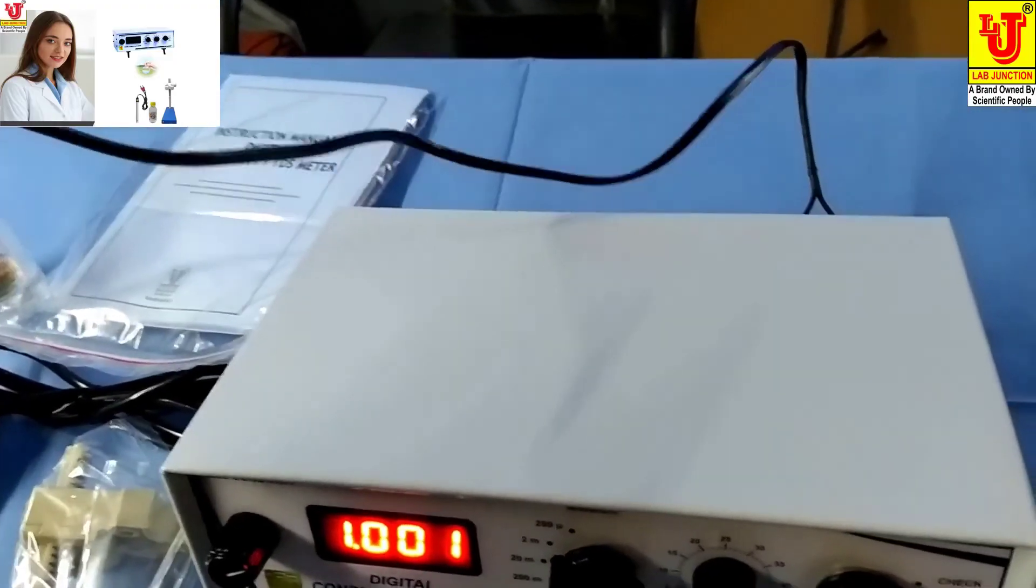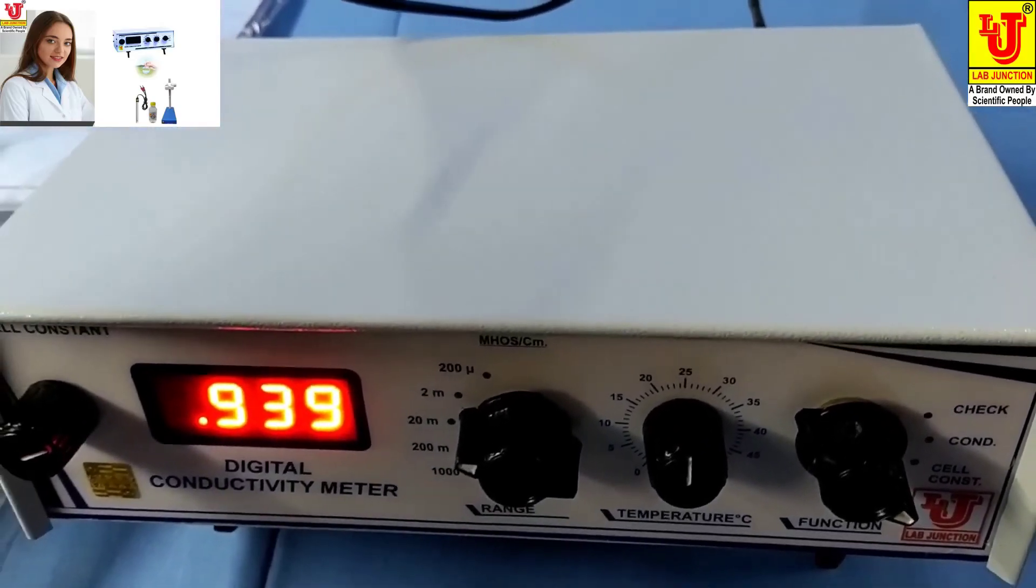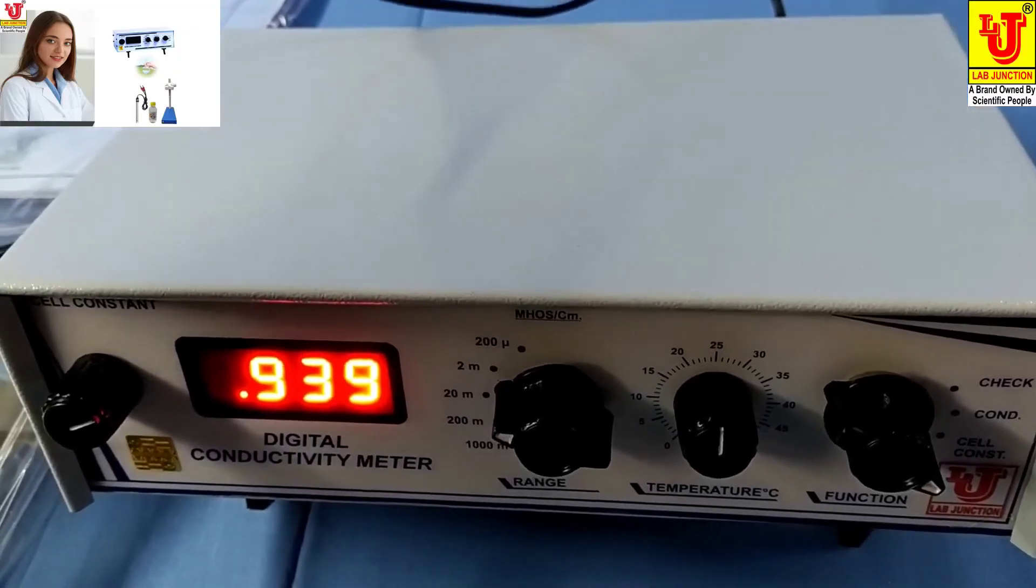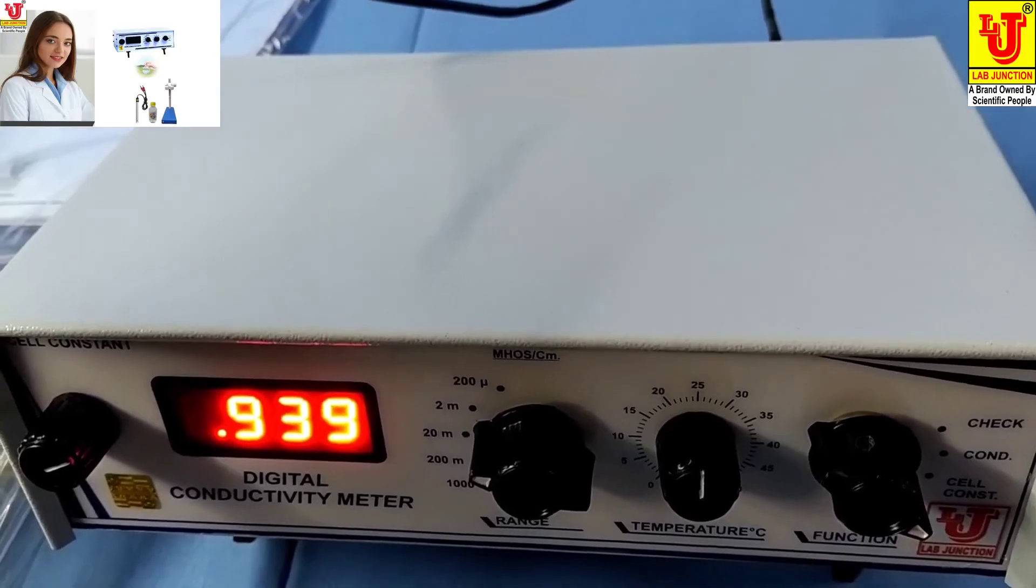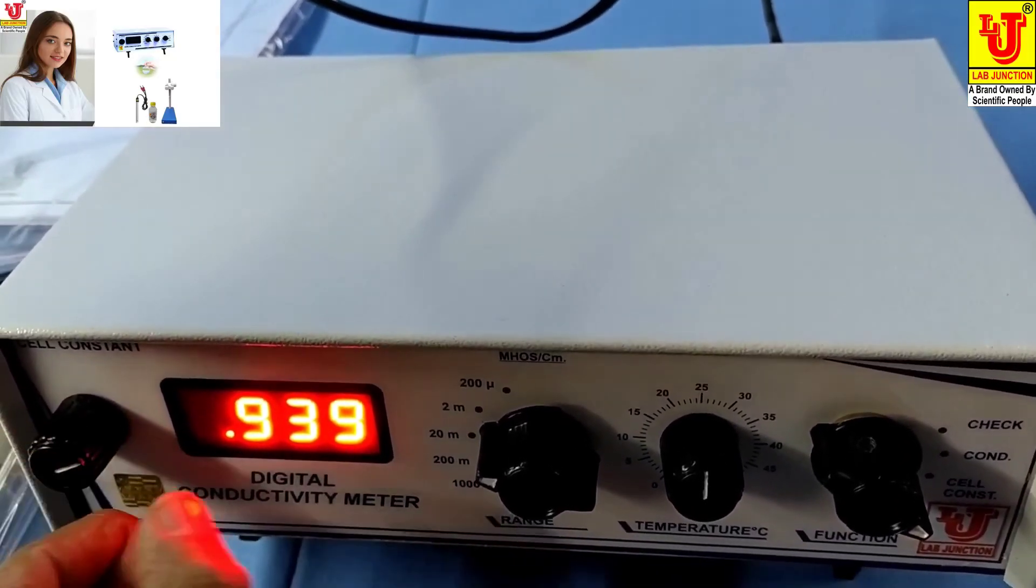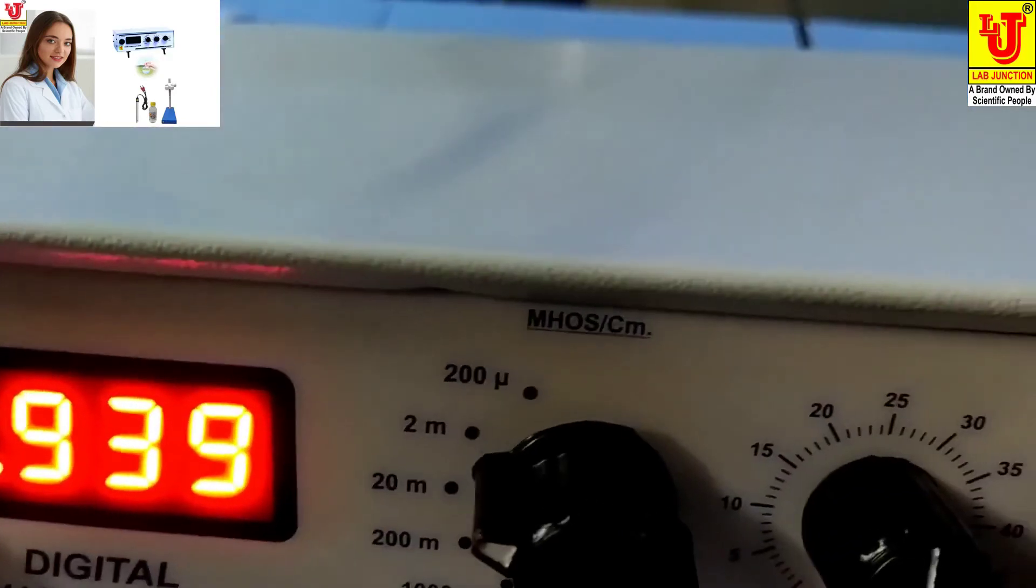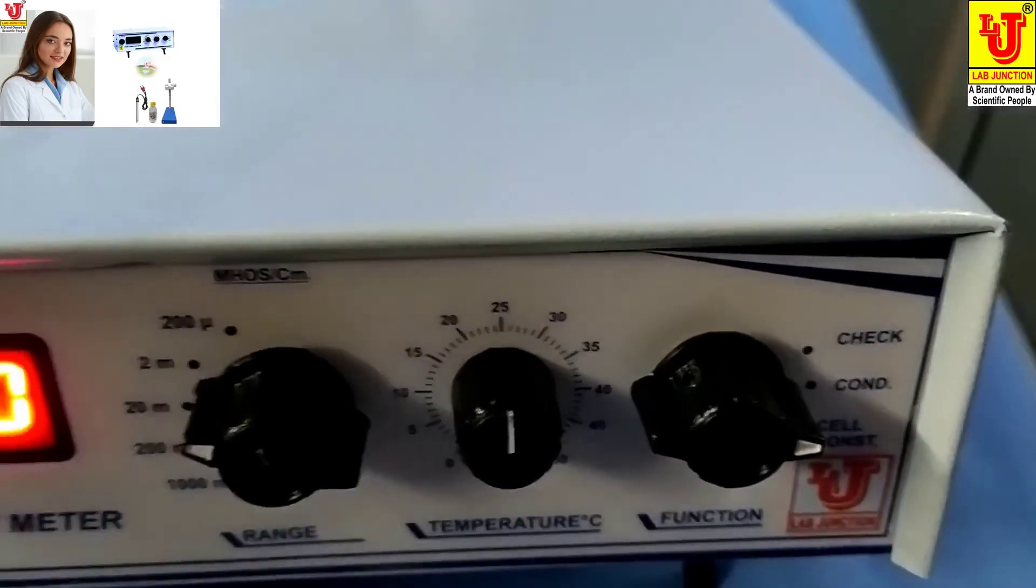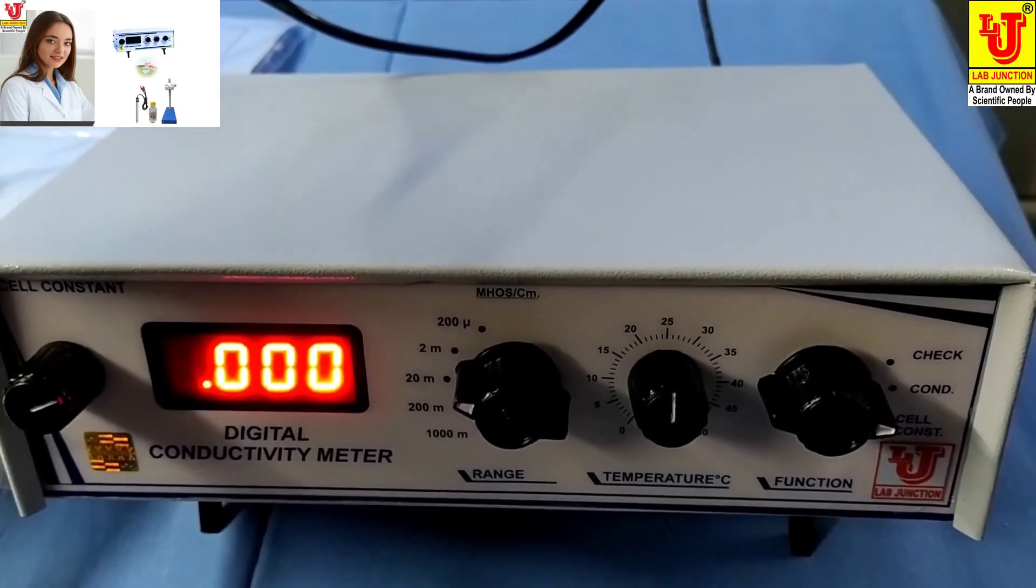Then go directly to cell constant. You have noted 0.939 in your notebook, so insert the same value using the cell constant knob and go to conductivity. Again, your digital conductivity meter is ready for use.